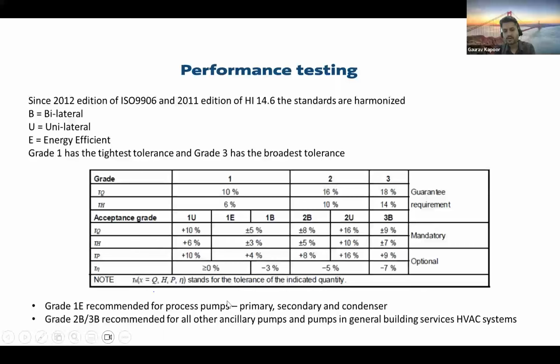Now for district cooling process pumps, the large size pumps, grade 1E is recommended, which you can see here, which says the flow can be plus minus 5% of the data sheet or the decided data sheet, the head can be plus minus 3%, the power can go plus 4%, but efficiency cannot go negative. It needs to be either the same or higher than what has been given in the data sheet. So grade 1E is generally recommended for process pumps, whereas for other ancillary or general pumps, grade 2B or 3B is easily used.